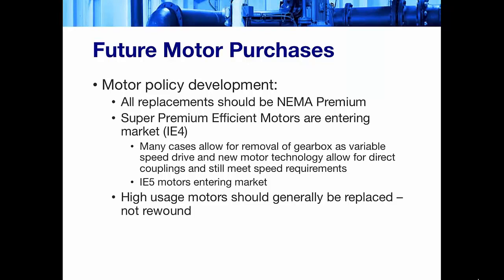There are also super premium efficiency motors that are coming out in the future, and some motor manufacturers are already claiming them. An important thing about these is that they have a different type of winding, and they can go much slower with variable frequency drives than most common motors on the market today. There are some applications where gearboxes can be removed, and that is a huge leap forward in efficiency. This is mostly being done on cooling towers, but I would suspect it starts to move into the water and wastewater market in the coming years.